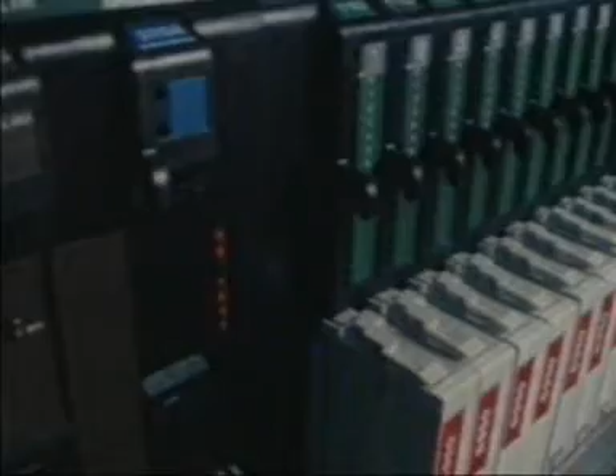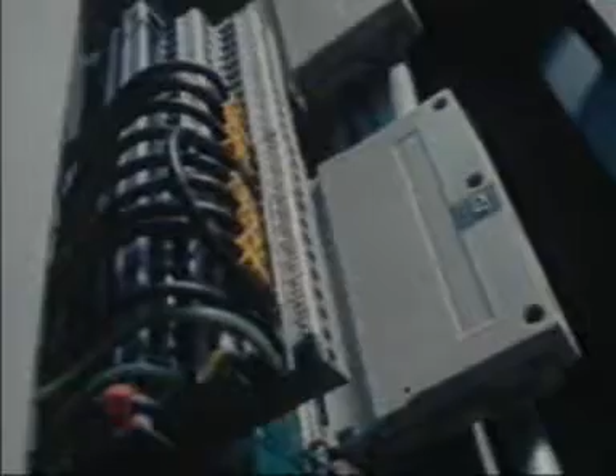Information is gathered in the cabinets built next to the control device sets. These cabinets were built in collaboration with CGEE-Alsthom. They include acquisition boards, which gather the measurements and convert them into data. A FIP communication board reads this information and forwards it through a coupling box every 20 milliseconds to the entire FIP network.